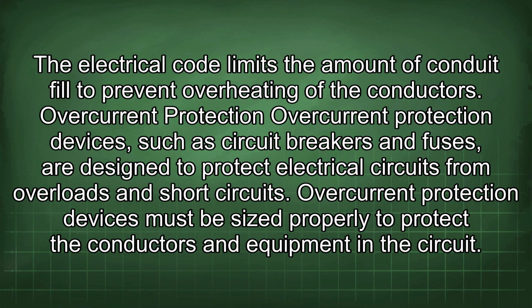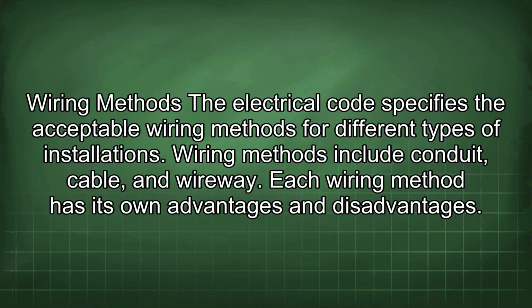Overcurrent protection. Overcurrent protection devices, such as circuit breakers and fuses, are designed to protect electrical circuits from overloads and short circuits. Overcurrent protection devices must be sized properly to protect the conductors and equipment in the circuit. Wiring methods. The electrical code specifies the acceptable wiring methods for different types of installations. Wiring methods include conduit, cable, and wireway. Each wiring method has its own advantages and disadvantages.